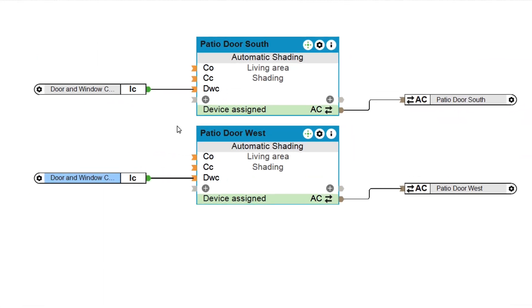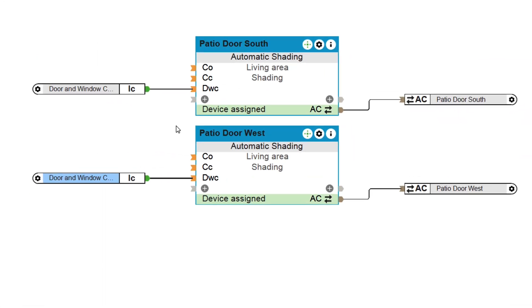What's very important now is that the input signal is reversed. Because if a window is closed, the contact delivers a 1, and if the window is opened, it delivers a 0. The input DWC, however, needs the exact opposite behavior. But that's not a problem — just hover over the input with your mouse, and as soon as the small black dot appears next to the cursor, a single click with the left mouse button will do the trick. A small dot will appear at the input DWC, which means it's reversed and we are ready to go.